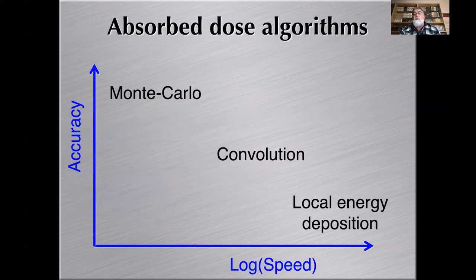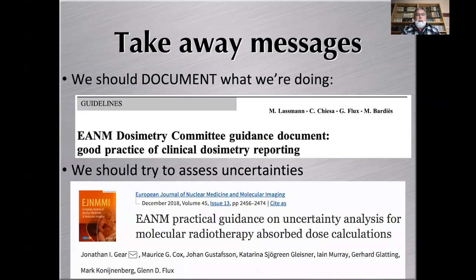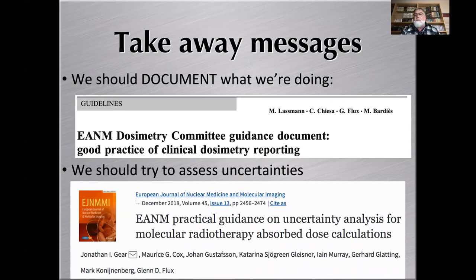The same applies for the absorbed dose algorithm to implement. Between local energy deposition, convolution, and Monte Carlo, there is no unique answer — it really depends on the clinical application and on the relationship between radiation range and spatial sampling of the geometry. To conclude this final lecture, what matters most is that we document what we are doing in order to ensure traceability of our results. Just do what you can with available tools and resources, but document what you're doing, so you can reprocess your data when you have more capabilities.